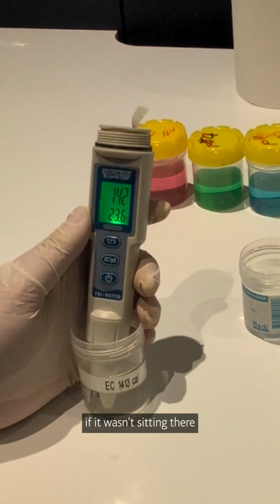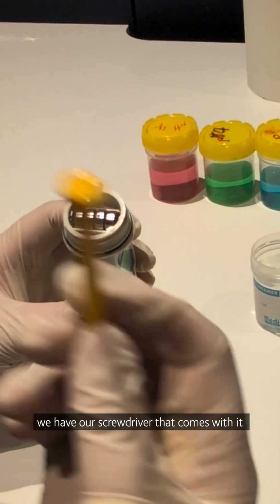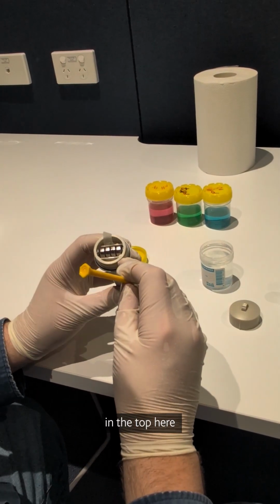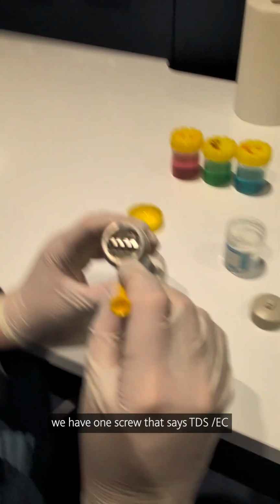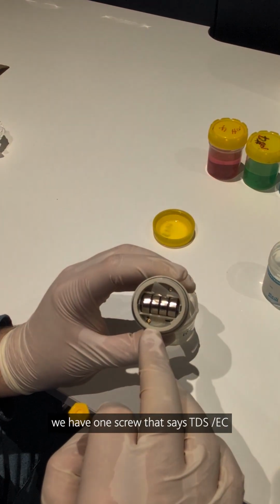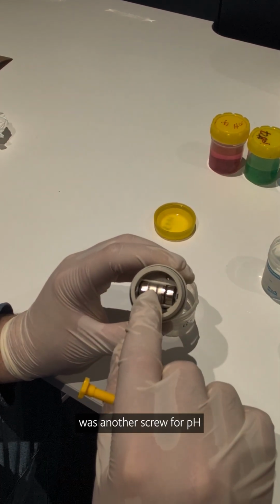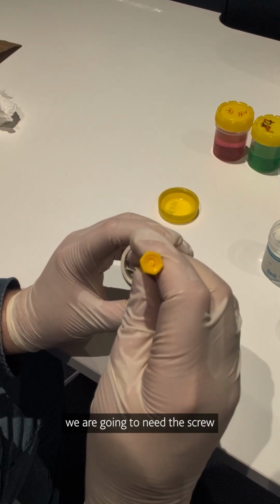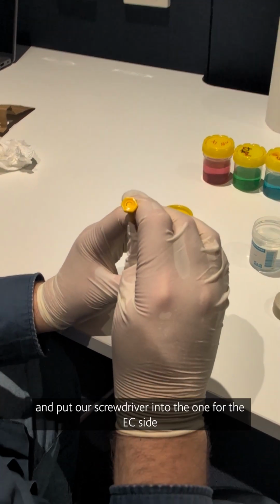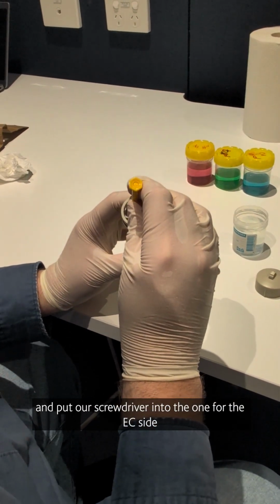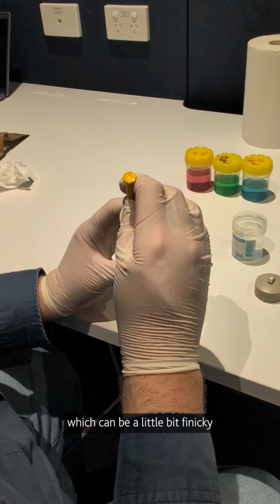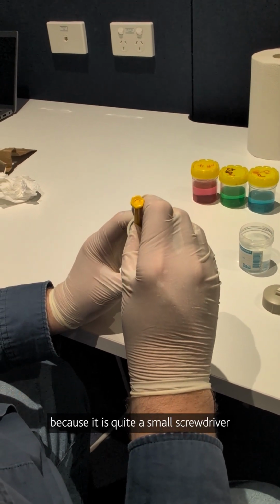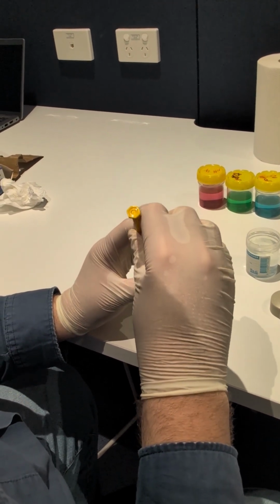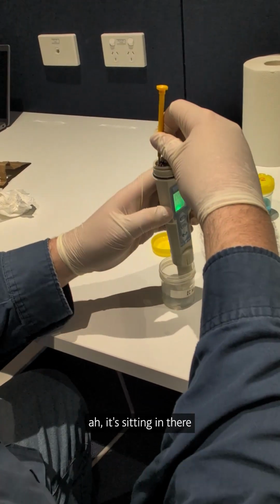If it wasn't sitting there, to change the calibration, we have our screwdriver that comes with it, and in the top here, we have one screw that says TDS/EC, or there's another screw for pH. We are going to need to put our screwdriver into the one for the EC side, which can be a little bit finicky because it is quite a small screwdriver. And that's sitting in there.